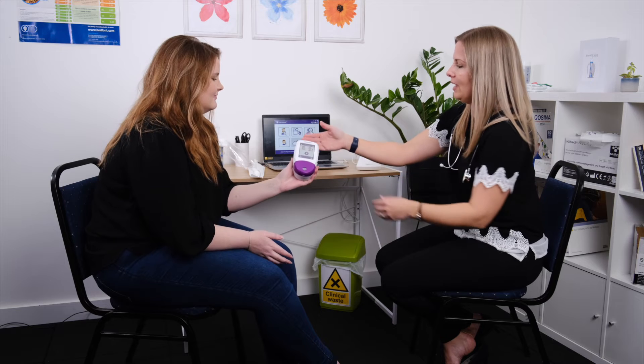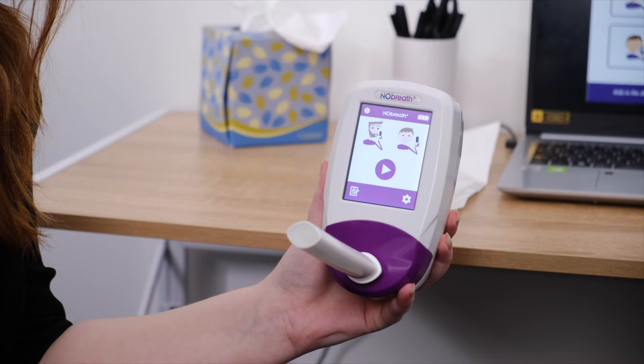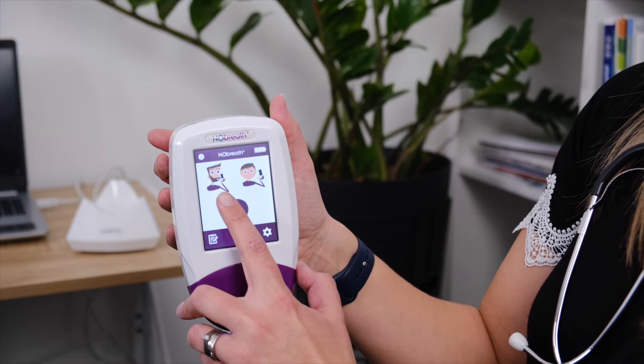Now that you're aware of any factors that might vary a FeNO result, it is time to take a FeNO test. First, turn on the NObreath device. Where possible it's preferable that the patient attaches their own mouthpiece. Attach a new mouthpiece to the monitor and select either the adult or child breath test icon from the NObreath home screen.